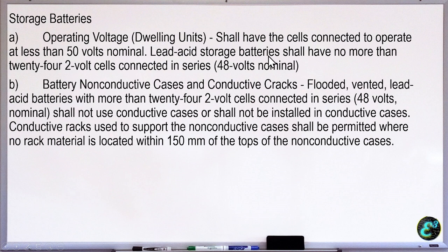So a lead acid storage battery shall have no more than 24 2-volt cells connected in series. When we say 24 2-volt cells, that is 24 times 2, so that is 48. So the maximum for a lead acid storage battery is 48 volts. Next, battery non-conductive cases and conductive racks.